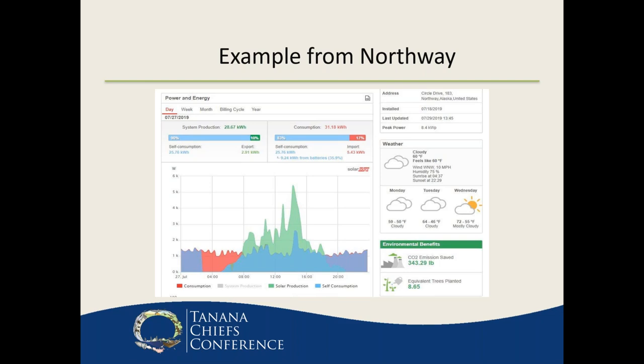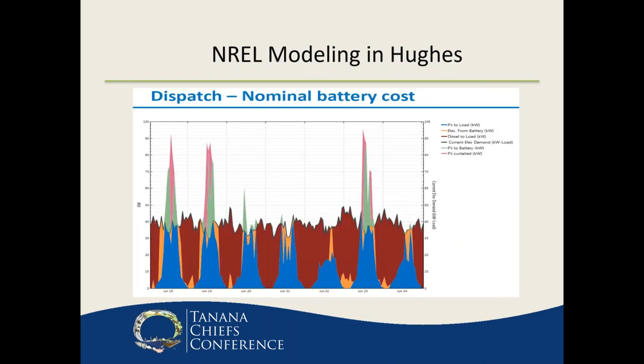Next slide. This is a graph model from our friends at NREL. They were able to assist us showing what that's going to look like. The blue is PV to load, the red is still diesel to load, so that's when we'll be needing to turn the diesels on. But when you're 100% reliant on diesel, this might look like a good start, and that's how we feel. It's not perfect, but we're not trying to get to perfection. We're trying to get to a better situation and less reliance on imported diesel, and this PV system definitely helps us do that.